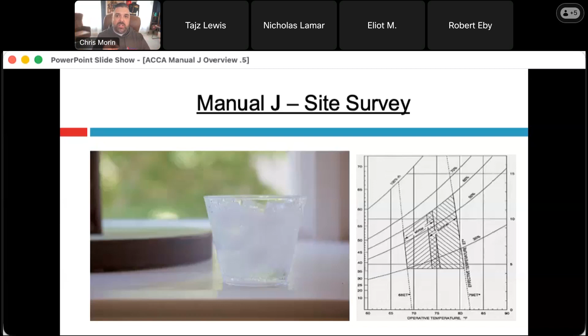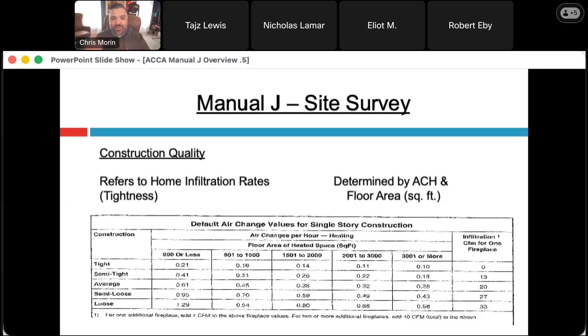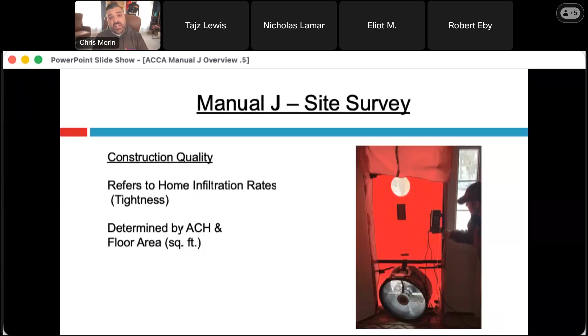Now, on to the next thing, infiltration. This is really important. Infiltration is determined by the air changes per hour and the floor area or square feet within Manual J. Keep in mind, this is not an ACH 50 number that's in there. Most software, if you enter an ACH 50 number, is going to do the calculation based on much less wind, right? So the numbers you'll see in these charts are much lower than what you would normally see for code purposes, like less than 3 ACH for 2021 IECC numbers, right? Keep in mind, if you do a blower door test on an existing home, you'll get really accurate numbers and you can enter that into your software. If you don't, you're going to have to take an educated guess, or if you have a new construction, you need to know what the target is, right?